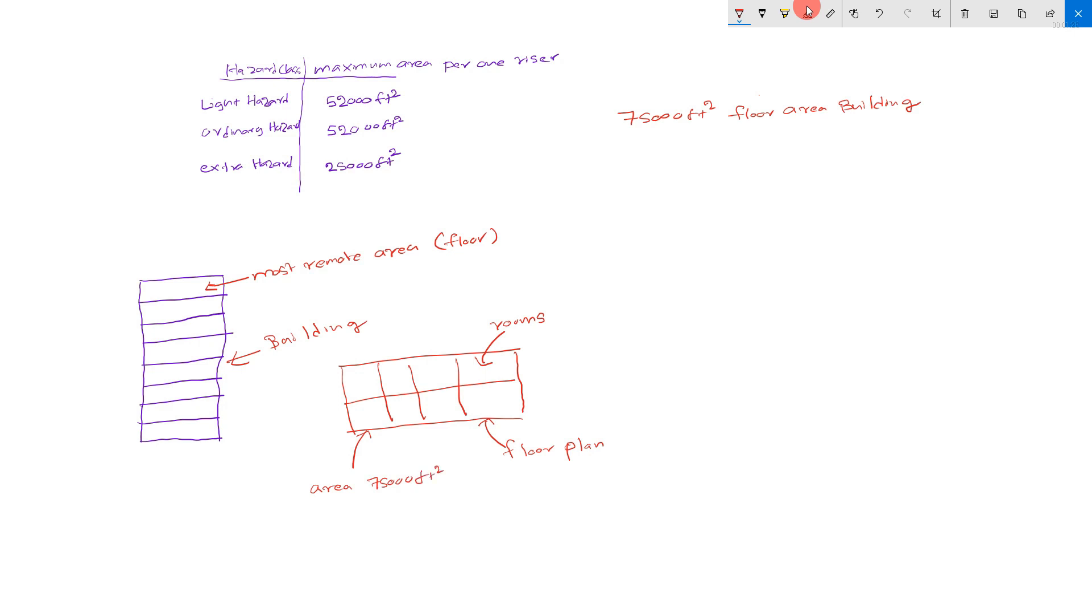According to NFPA, light hazard maximum area per one riser: 52,000 square feet. Ordinary hazard: 52,000 square feet. Extra hazard: 25,000 square feet.